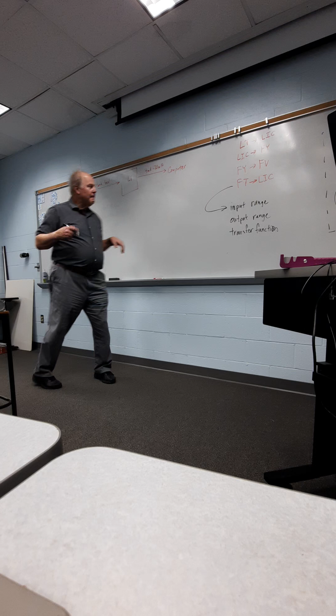Why top of the tank? It's as far as we go in a tank. Put more water in it, what happens to it? It flows out of the tank. So we don't measure anything higher than the top of the tank. So we were way back at proportional band, 2 days ago. It is a limit on a range. So what's our proportional band limit on a tank? Well, it's going to be 0 inches to 10 inches.